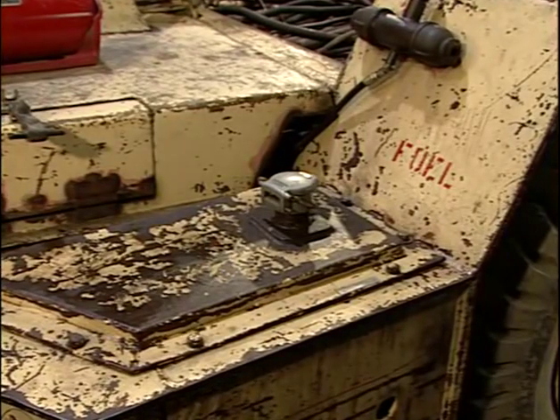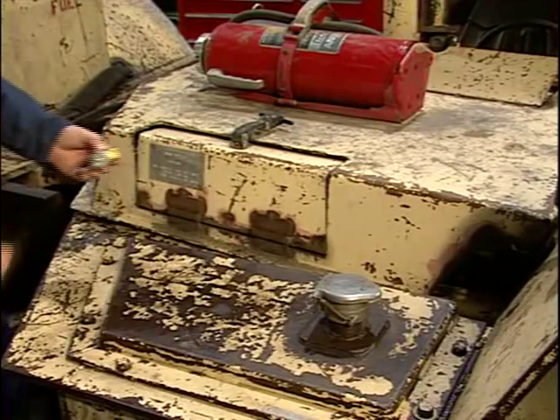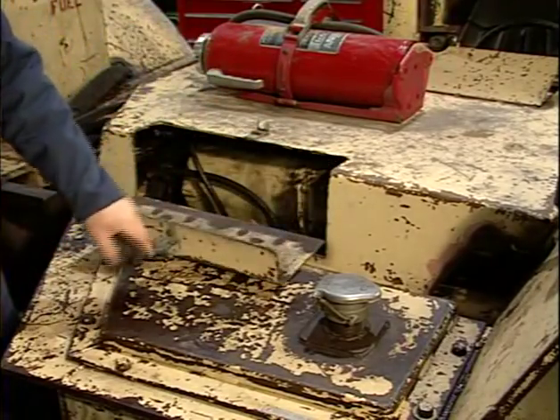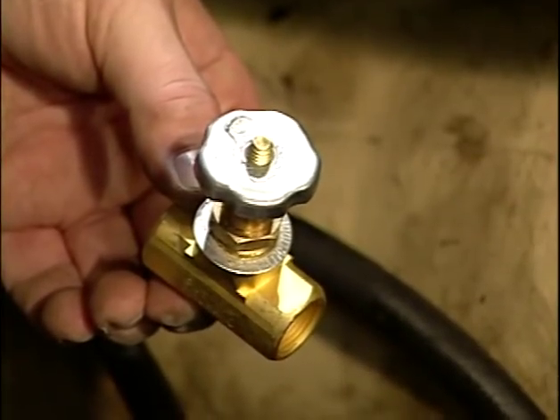Although not installed here, all fuel tanks need fire suppression coverage and, if automatic, fire detection. This lube truck does not have a manual shutoff valve. The manual shutoff valve must be installed in the fuel system as close as practicable to the tank.